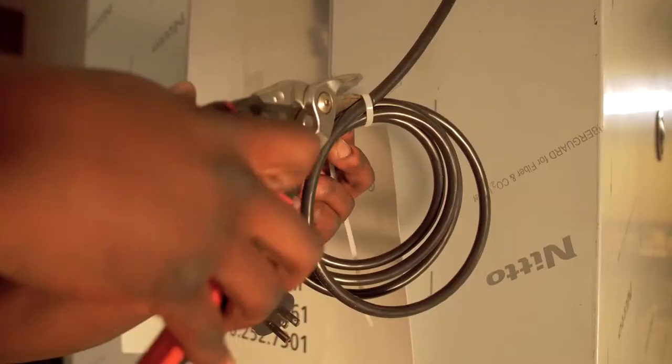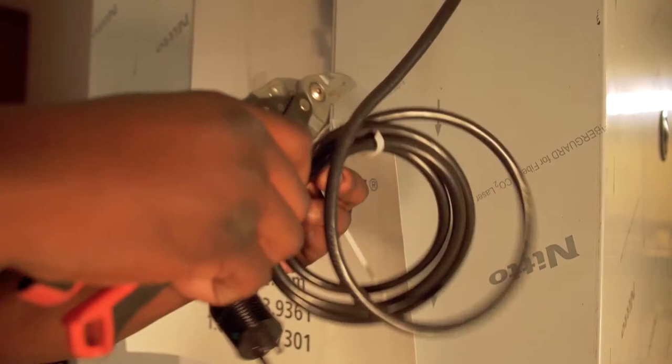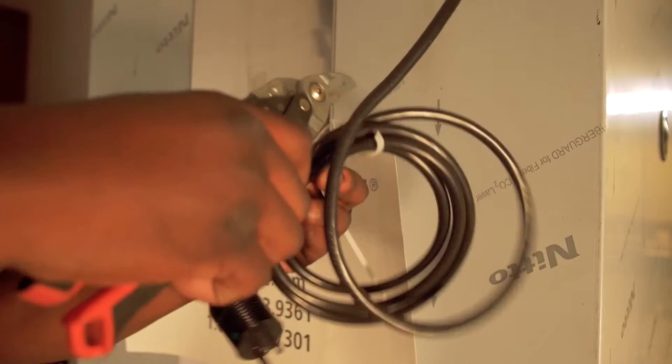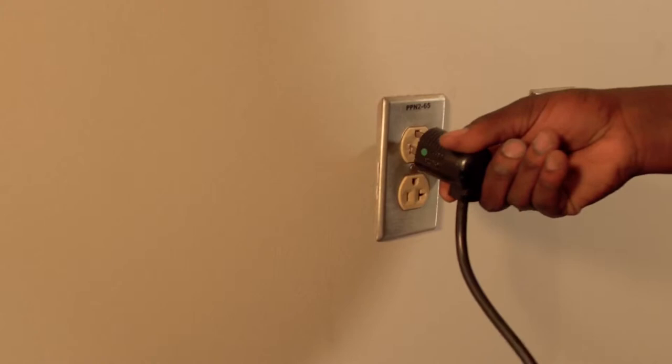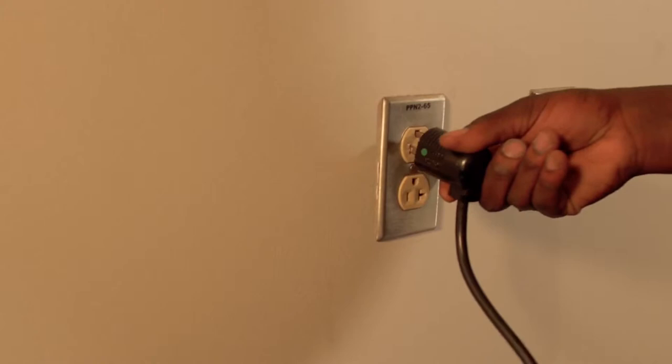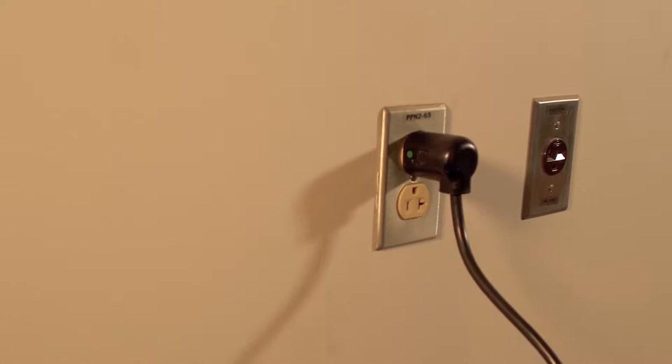Wheel the refrigerator into the installation footprint as directed by the site contact. Locate the power cable on the back of the unit, carefully cut the zip tie, and plug the power cable into the outlet within the installation footprint to confirm power of the refrigerator.